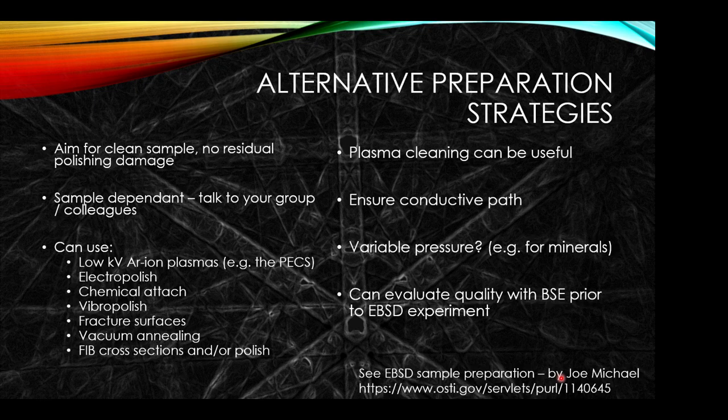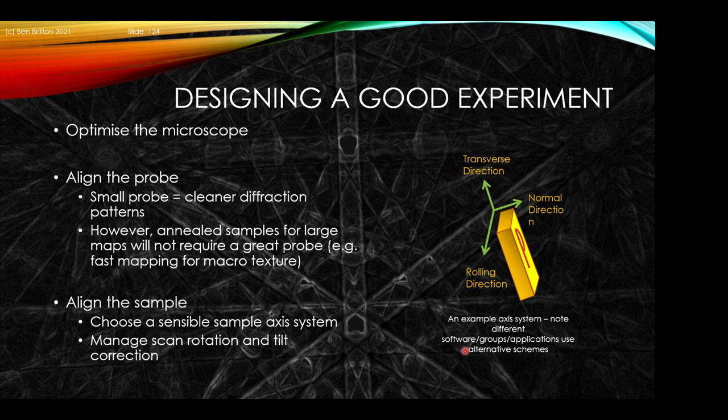There are a whole range of cool tips and tricks by Dr. Joe Michael presented in a Sandia paper — well worth a look. Once you've got good sample prep you need to optimize the microscope. You want to align the probe — see the SEM lecture notes on how to do that. A smaller probe gives you cleaner diffraction patterns, but do recall that annealed samples with large maps do not need a great probe, so you can use a cheaper microscope for those. You'll want to align the sample as well as possible, choose a sensible sample axis system, and manage and correct the scan rotation and tilt correction — see earlier sections of this lecture for that information.